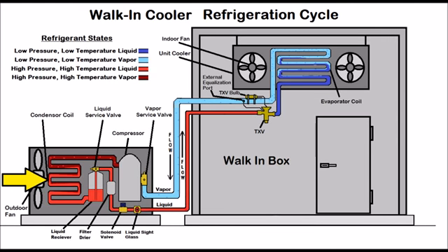And what happens is that would end up limiting the amount of space on that coil for the saturated state. The saturated state is liquid and vapor, both existing at the same time, and like I said before, that is where most of the energy is being rejected out of the refrigerant and into the outside air. So having a large saturated state in the evaporator coil and at the condenser coil is crucial to a refrigeration system working properly. You have to have complete vapor heading into the compressor. You want to make sure that you don't have any saturated refrigerant heading into the compressor or just straight liquid heading into the compressor. It has to have complete vapor only heading into that compressor.